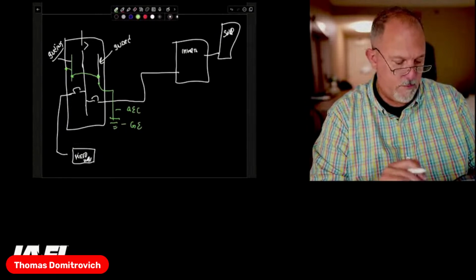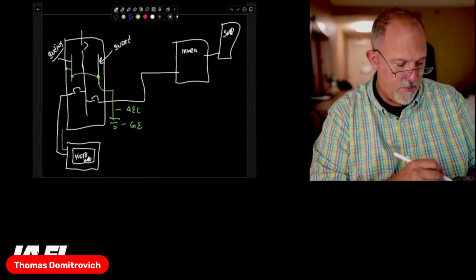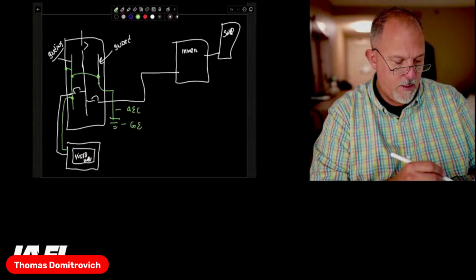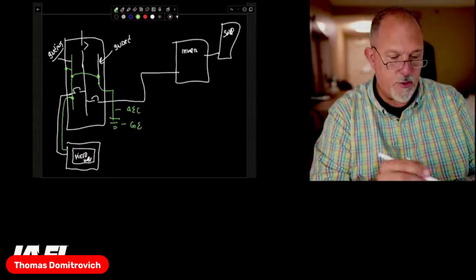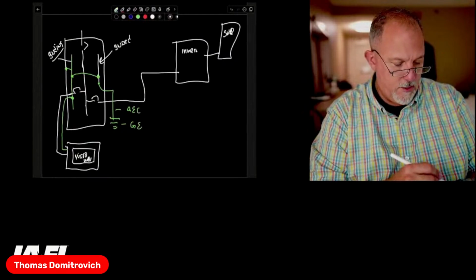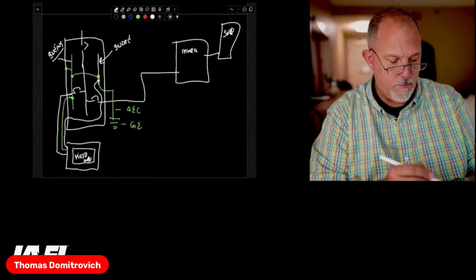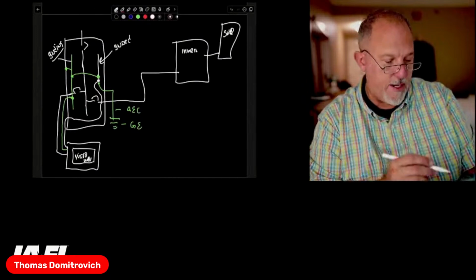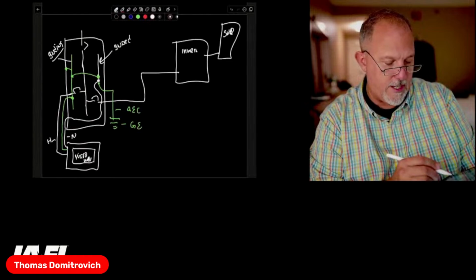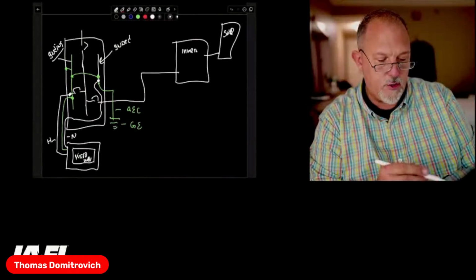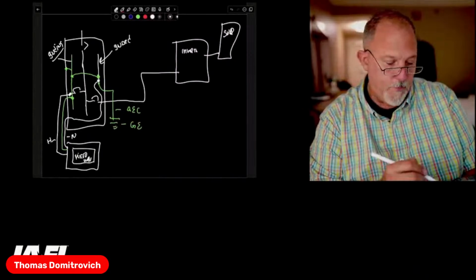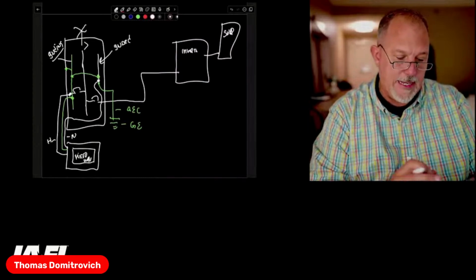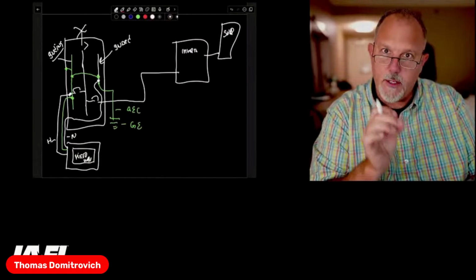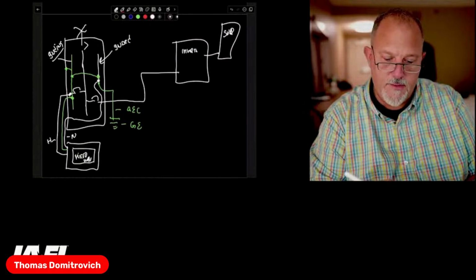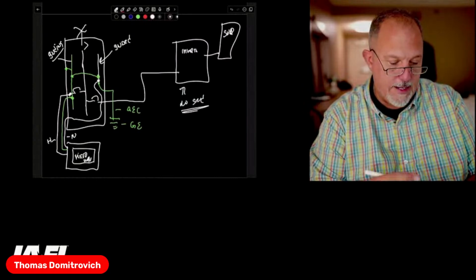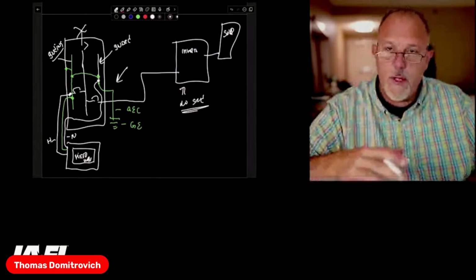I come out of this equipment and I would go to the ground, and then I would have a hot and the neutral. The neutral, I'm going to draw a white. The neutral would come back and come up to this bar right there, right? So this is my neutral, this is my hot. My hot goes to the circuit breaker. My neutral goes to that bar, which takes it back down to ground. So if I lose my utility, I still maintain the integrity of bonding the neutral to the ground back to the inverter. Even if I have no ground here, I still have a ground there reference that neutral is tied to.